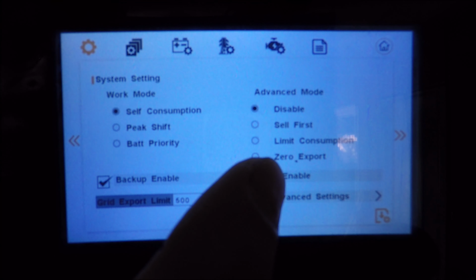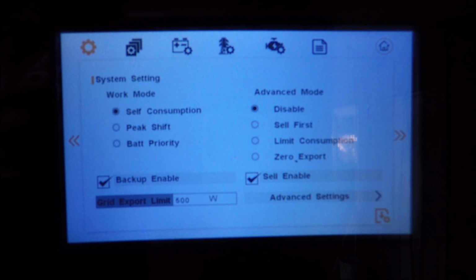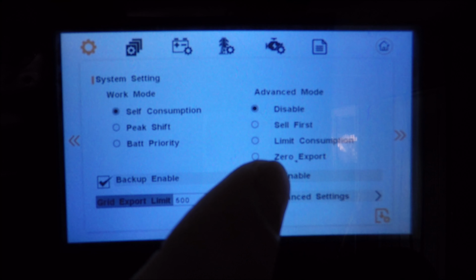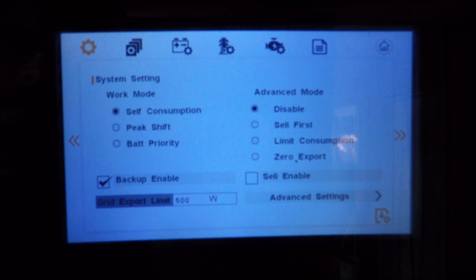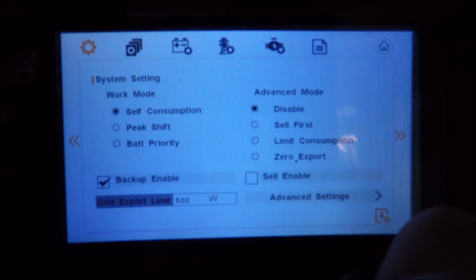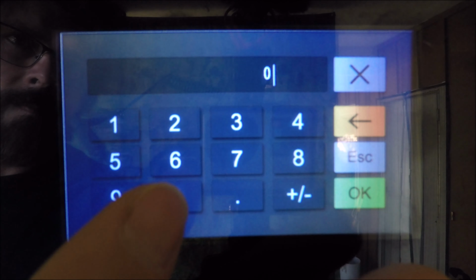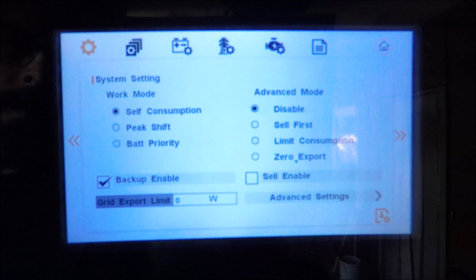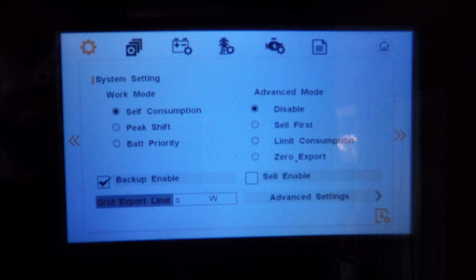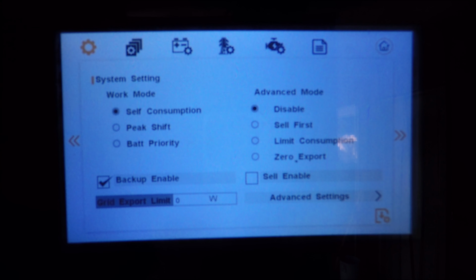We are going to ensure that sell enable is unchecked. Many times with the system, it will come in default with it checked. As long as you uncheck the box, it will not sell back to the grid. We're going to set our grid export limit to 0. This is also going to ensure that we do not send any power back to the grid. This is an initial configuration for basic off-grid setup.